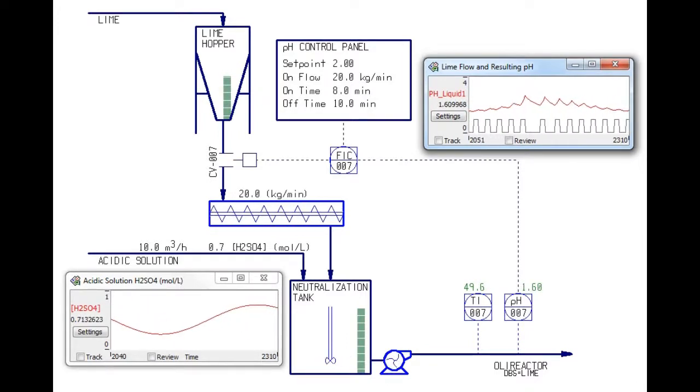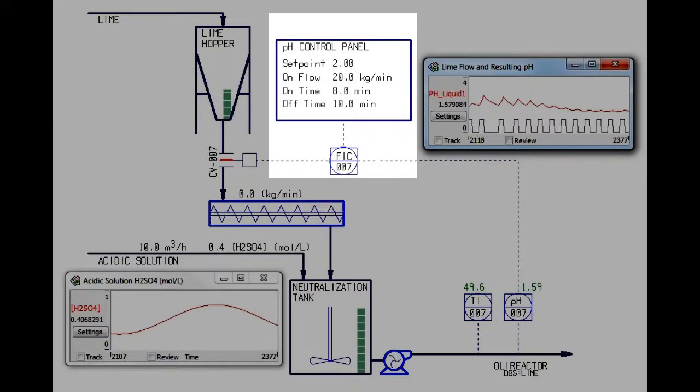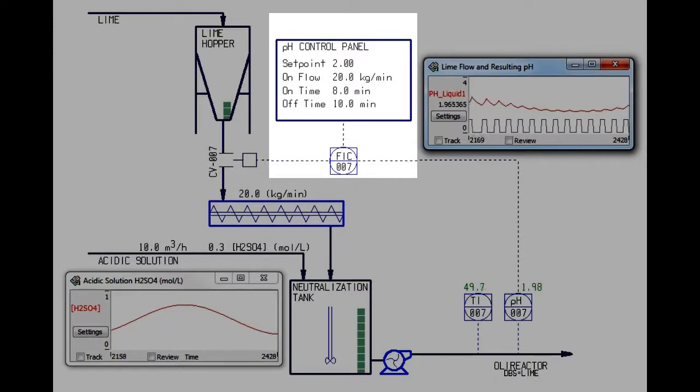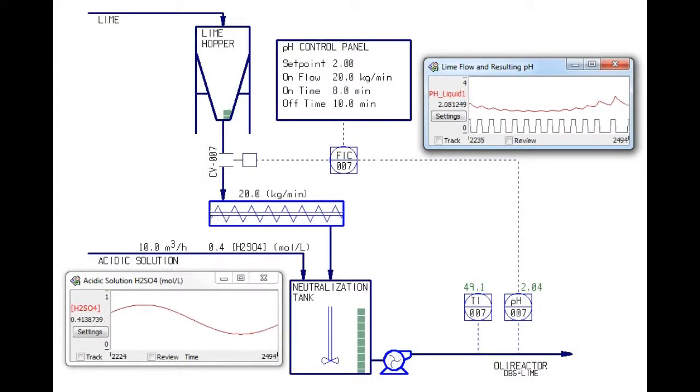To control the pH, I have set up a simple on-off pH controller that feeds lime in for 8 minutes and then lets the tank mix for 10 minutes. If the pH is below the setpoint, more lime is fed in on that schedule.